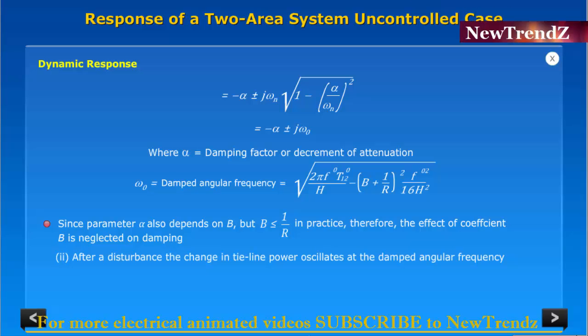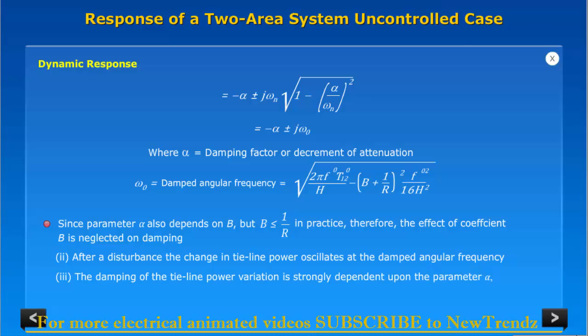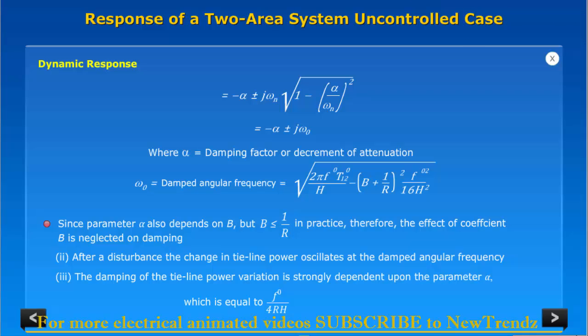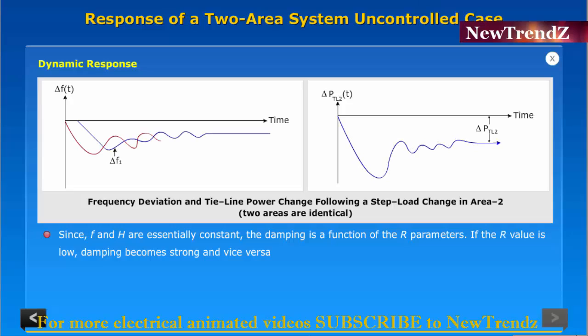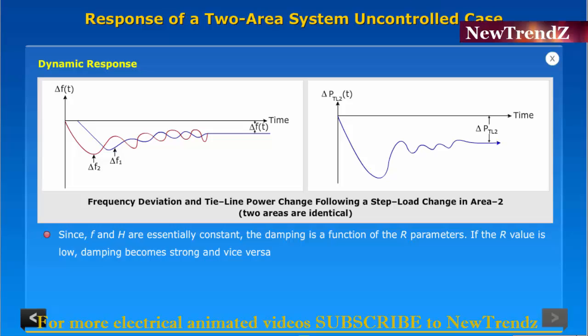After a disturbance, the change in tie line power oscillates at the damped angular frequency. Damping of the tie line power variation is strongly dependent upon the parameter alpha, which equals f0 divided by 4rH. Since f and H are essentially constant, the damping is a function of the r parameter. If the r value is low, damping becomes strong, and vice versa.